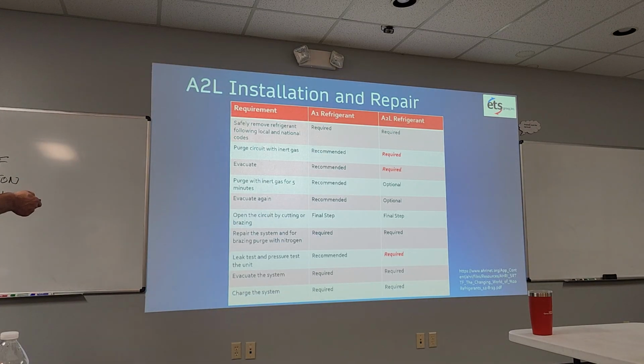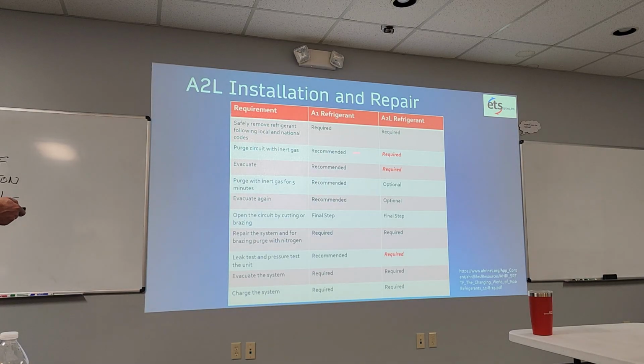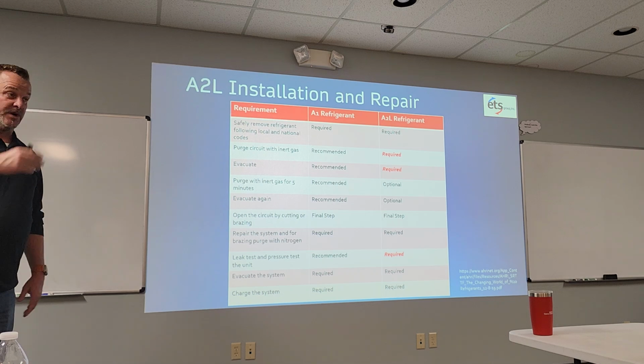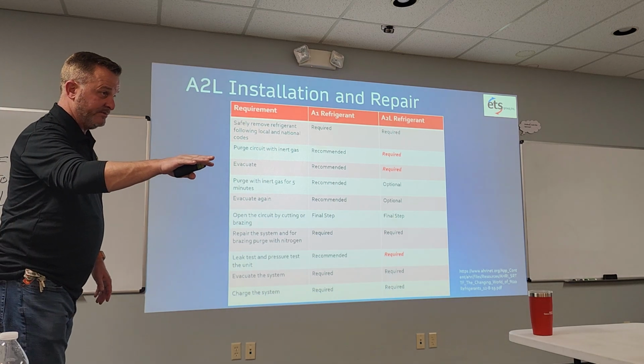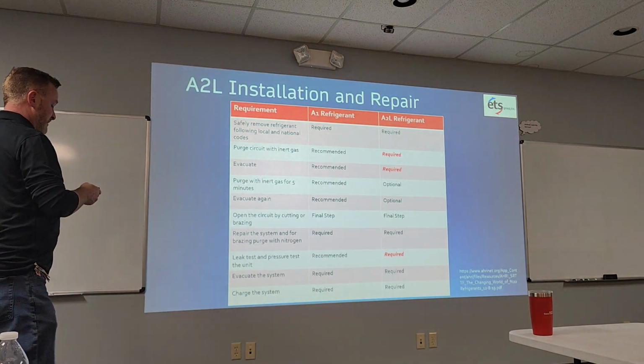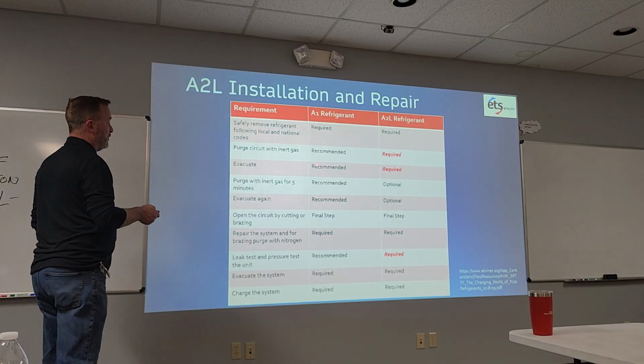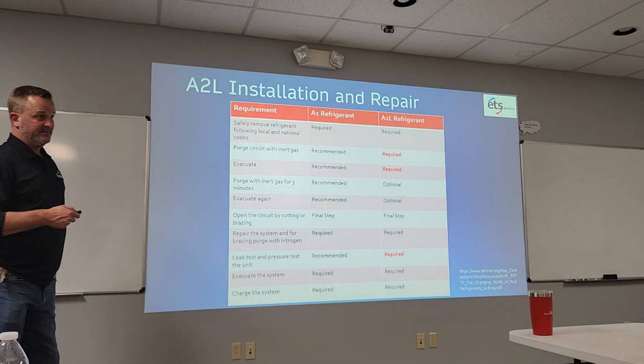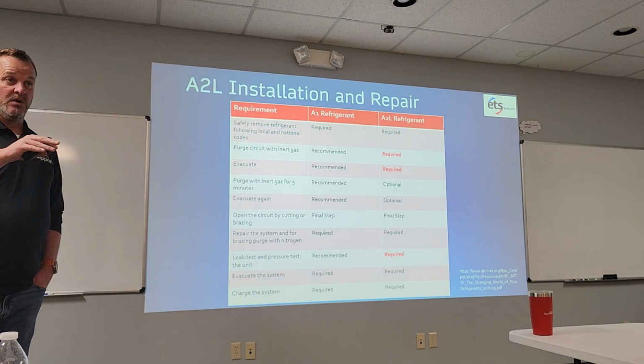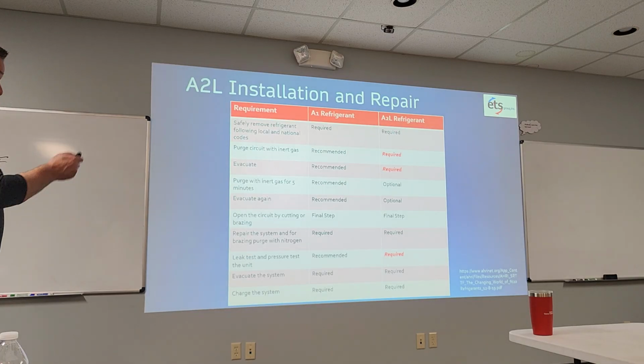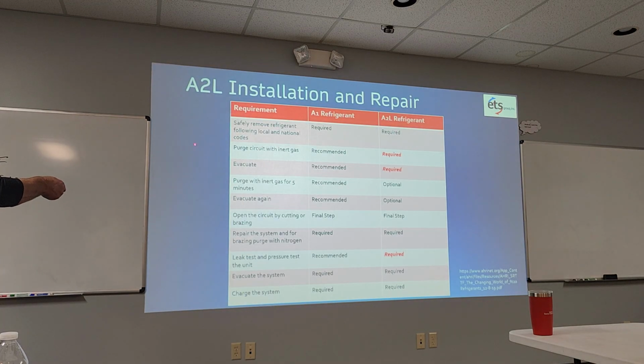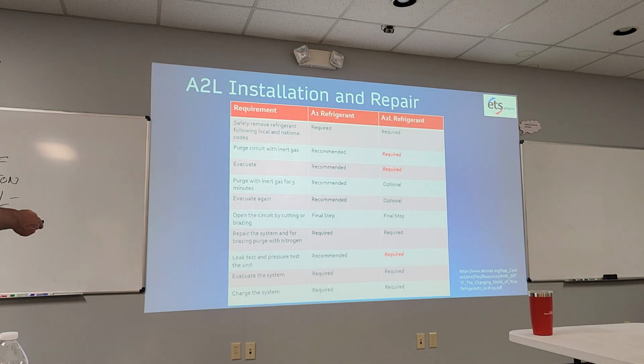What's new is after we recover that refrigerant, we're going to purge the circuit with inert gas, oxygen-free nitrogen. So we recover, then we purge. That's a new step. Then after we purge, we're going to evacuate that system before we start working on it. So you're going to recover, you're going to purge, and you're going to evacuate. What they're doing is making sure we get everything out of there that we possibly can.